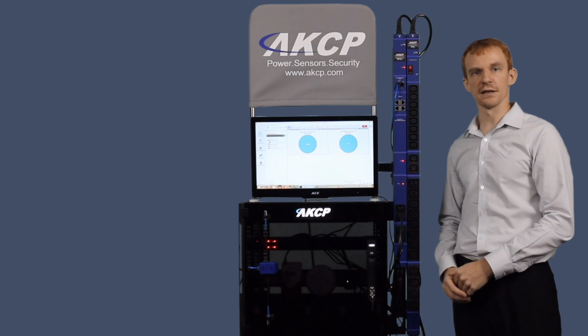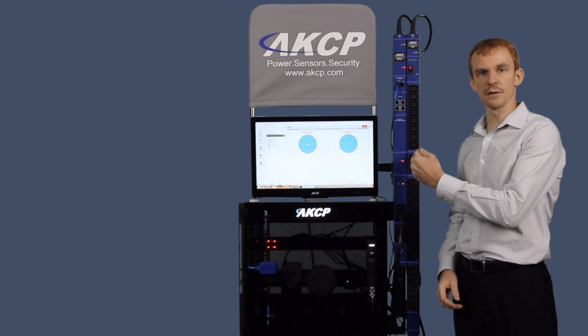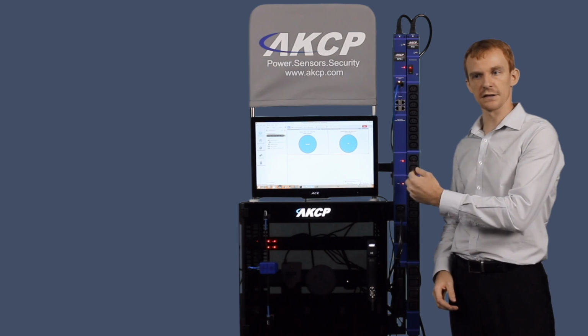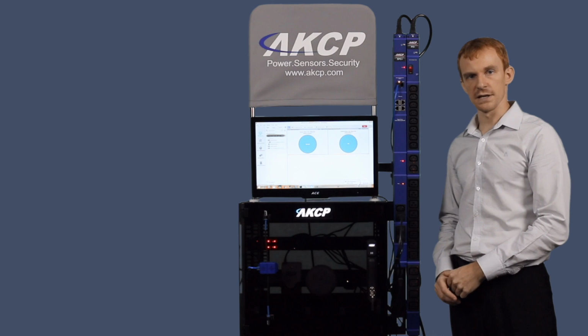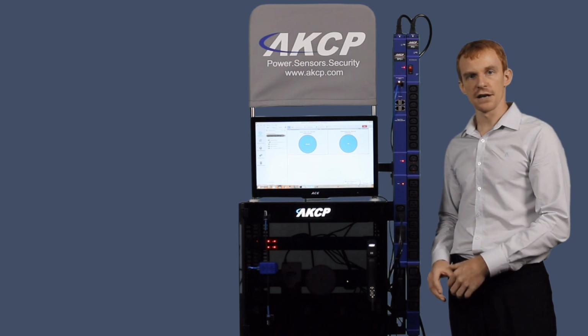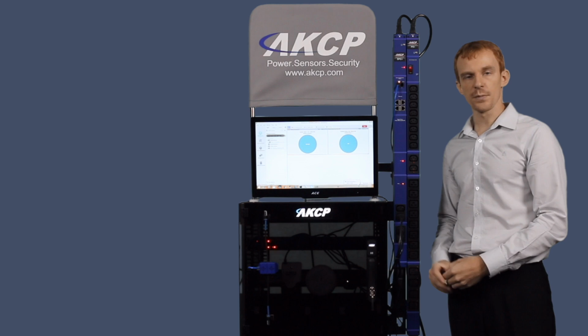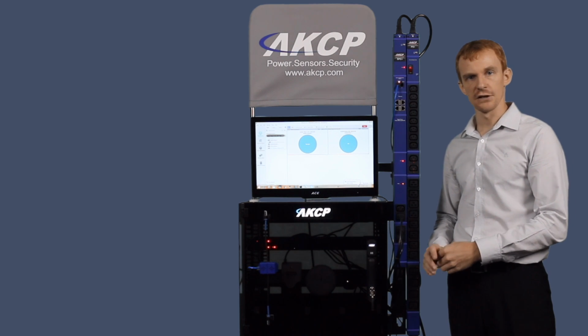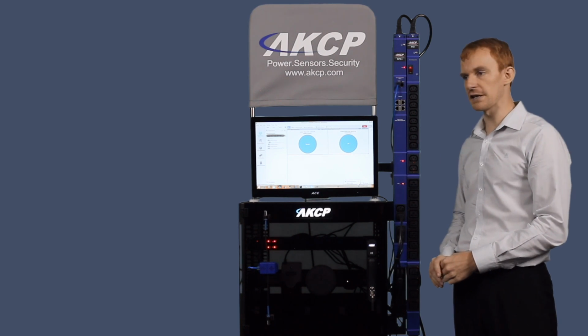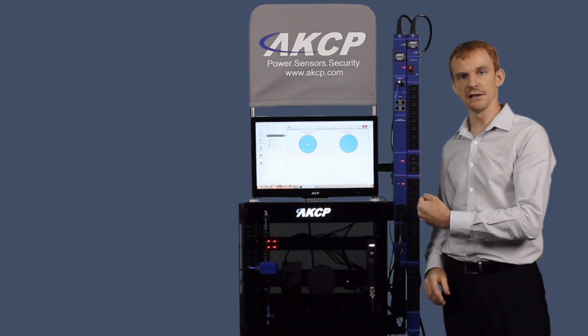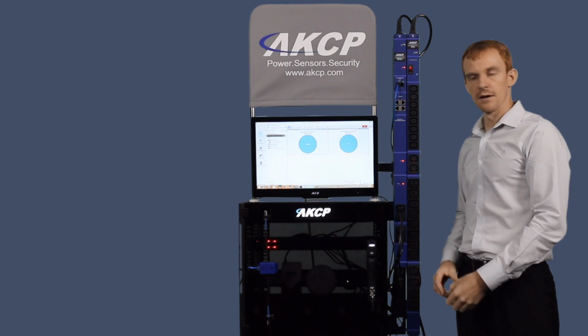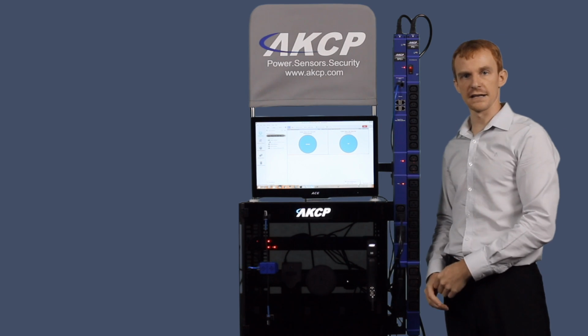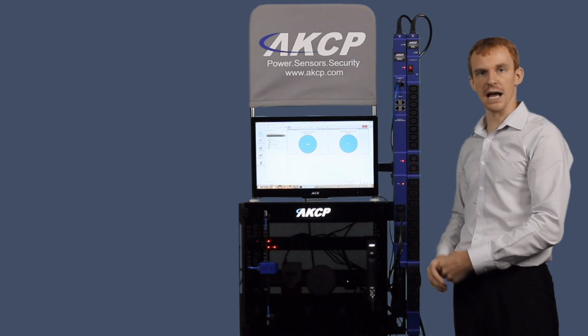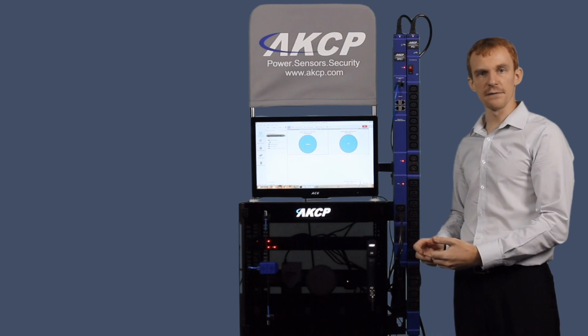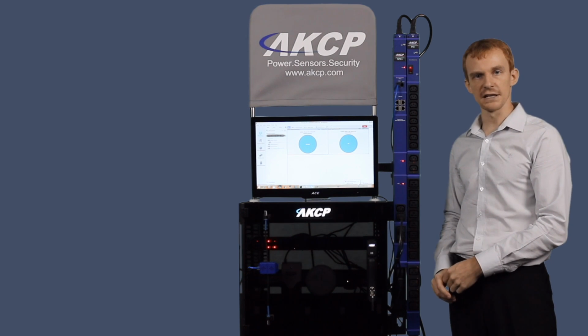The other advantage of using the power meter is that you can combine the data being collected by the power meter on the SPC Plus with data being collected by power meters connected to your air conditioning, and you can then calculate your PUE. Your PUE is the gold standard as to how efficiently your data center is running. The power usage efficiency will tell you how much you are spending on IT load compared to cooling load. By using our system together with our sensors such as the thermal map, you can then adjust your cabinet settings and cooling, thus saving you energy and making sure that you are not exceeding the ASHRAE recommended air intake temperatures for your cabinet.